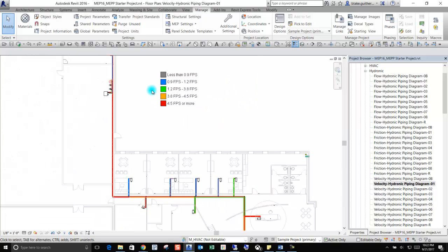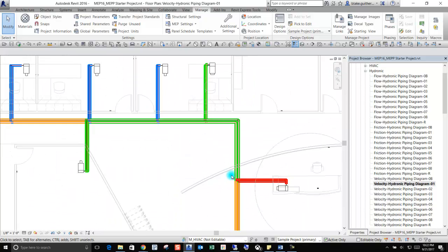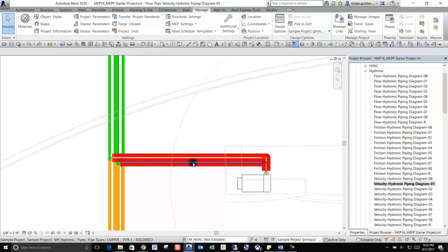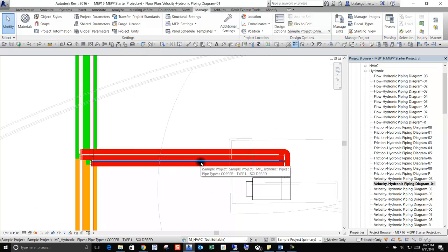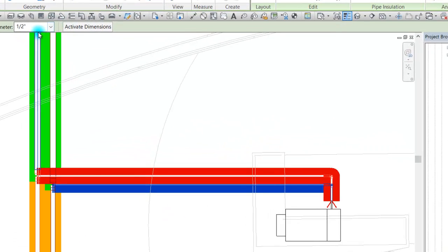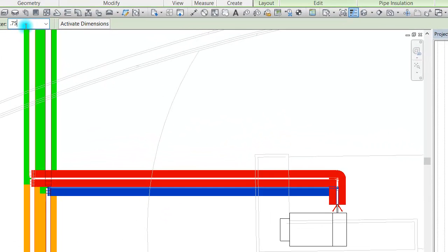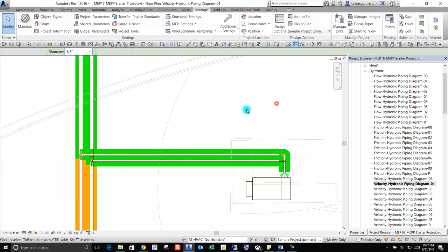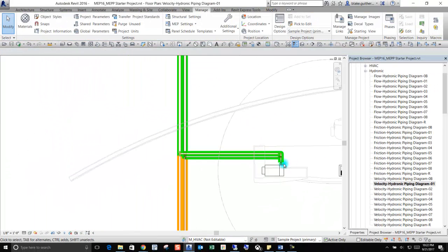If that was the case, you could use this view to pinpoint any sections of pipe that don't meet that tolerance. So like here's some runouts to a VAV box. Let's update those. So again, it's just another design tool to help you make sure you have the valid GPMs in your piping system before you go to size it.